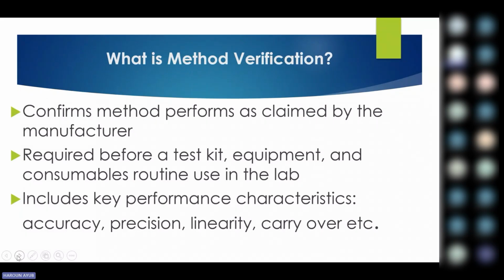They are already listed claims. So you'll have claims of accuracy, claims of precision, claims of carryover, and you need to do this to confirm that the analyzer is actually doing as intended. Some manufacturers will send you a report that comes with the analyzer, a checklist of the tests that they have done. It's also important for you to check aspects to do with, let's say, biosafety cabinets and laminar flows. You'll usually get a test report that claims the air pressure inside the equipment and so on. All those form part of your verification of the manufacturer's claims.